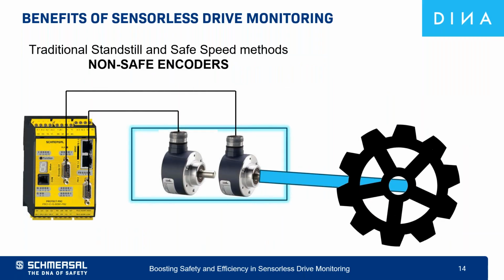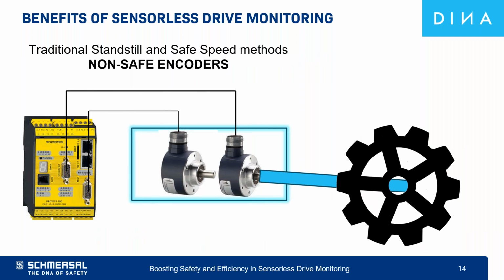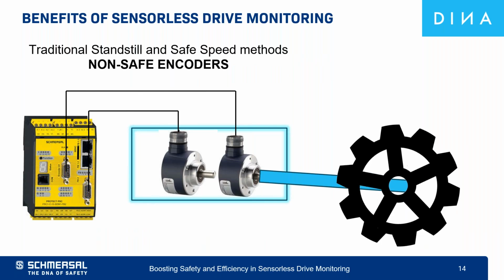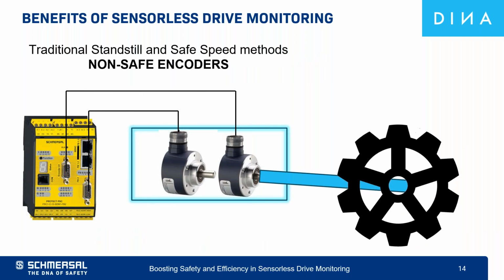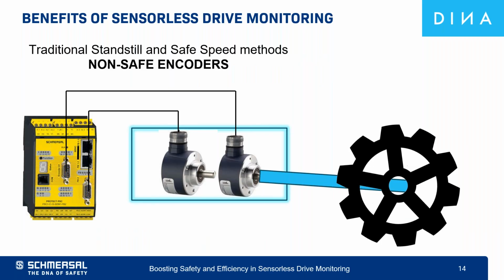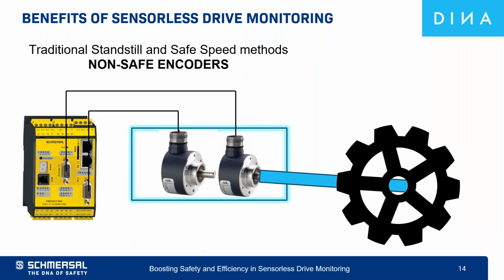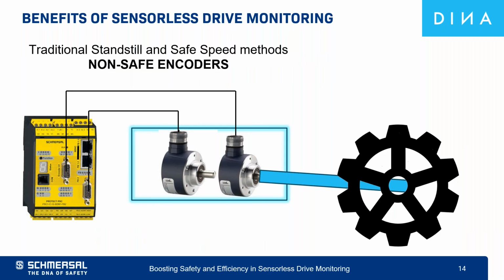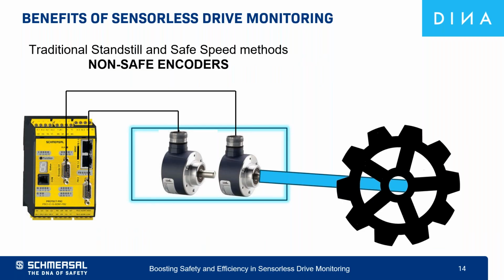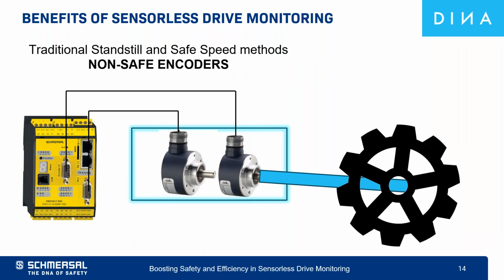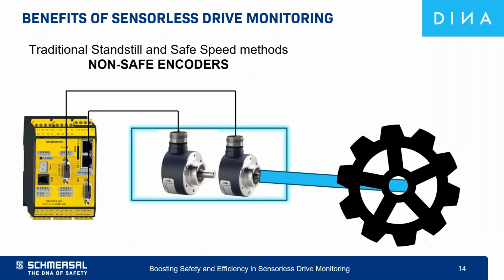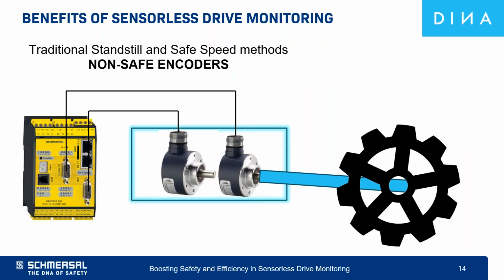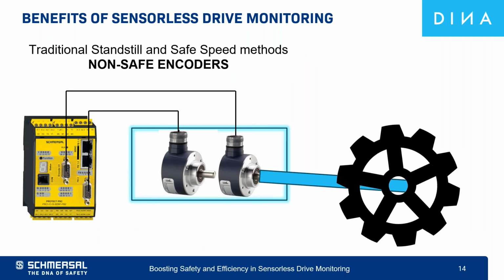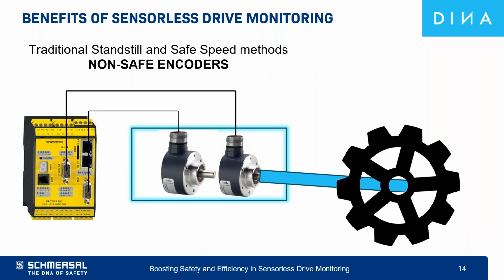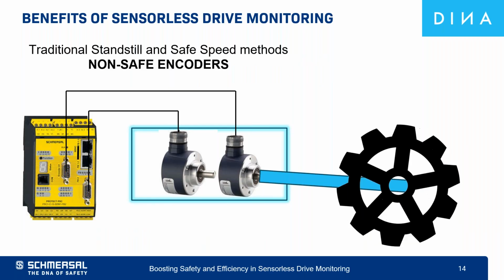Perfect. Okay, so typical drive monitoring in the past has been done with encoders on the end of a motor shaft or proximity sensors, which watch a cam or gear to detect movement of a hazardous motion. When using a non-safe encoder, you should use two encoders on a single shaft, monitoring the hazardous motion for redundancy. Non-safe encoders is how speed monitoring was done originally, due to the fact that safety-rated encoders were not available from many manufacturers until the last 10 years or so.